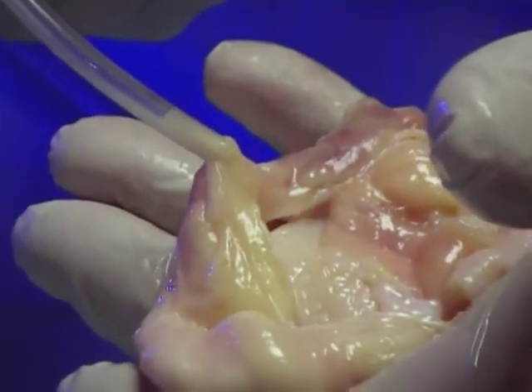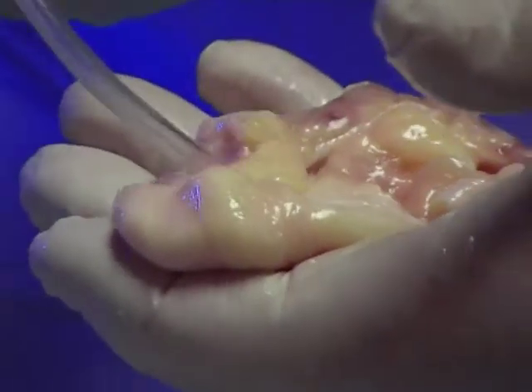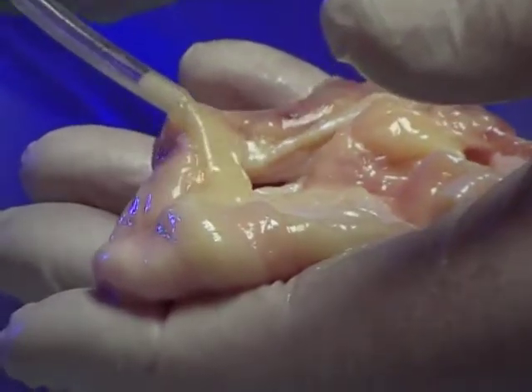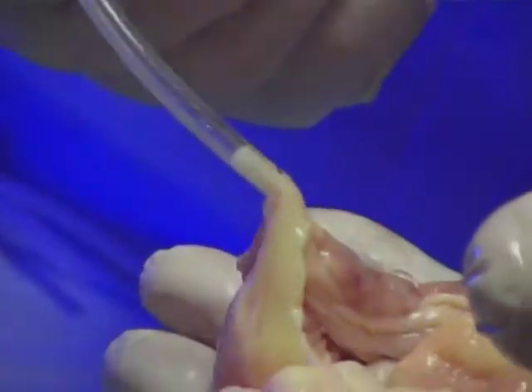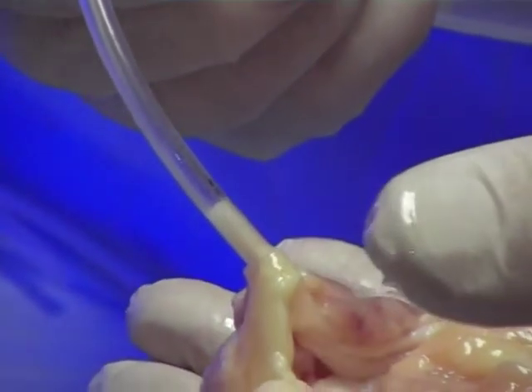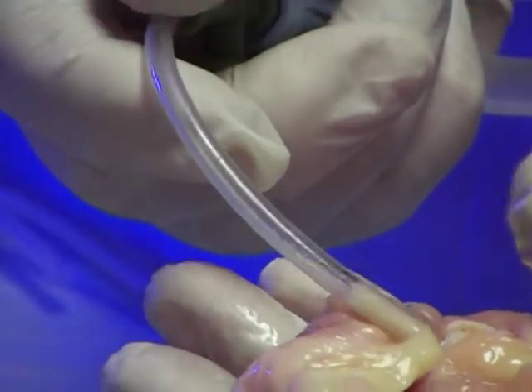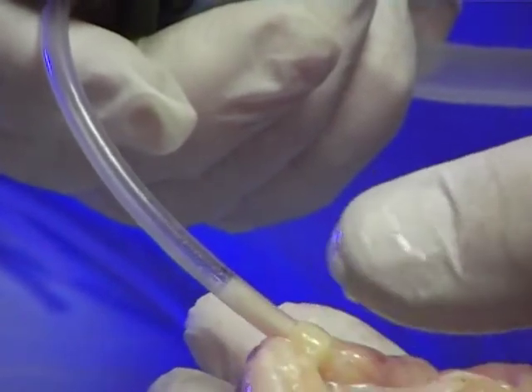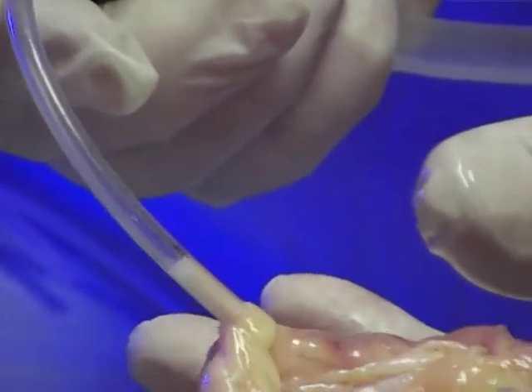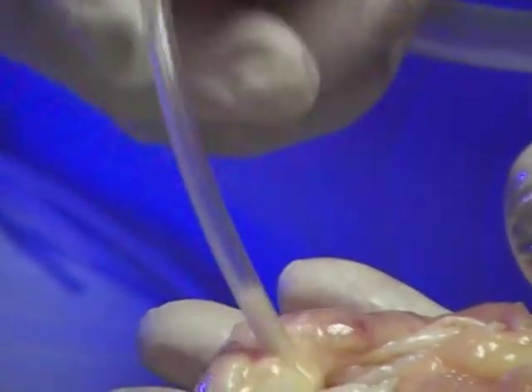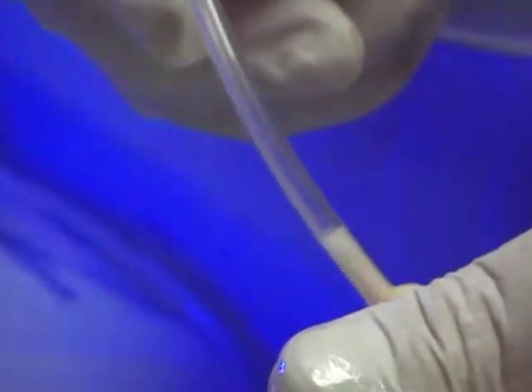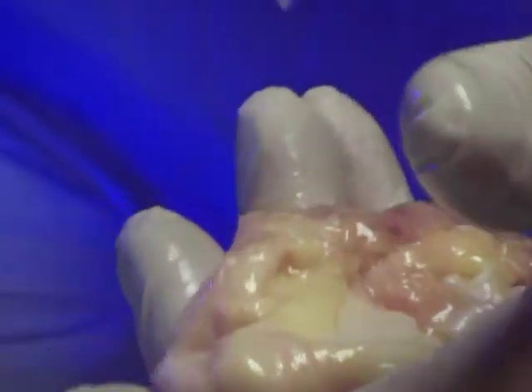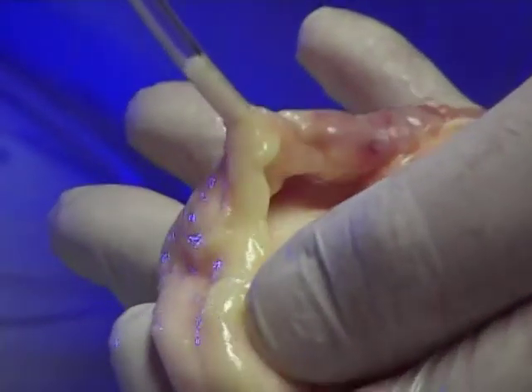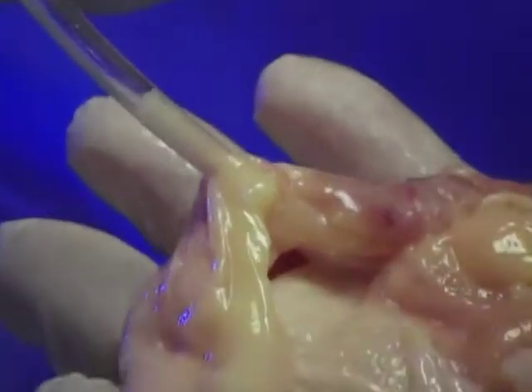It actually grabs more tissue. So in an effort to try and get the mucus out, now what's happened is I can almost lift this up. That's a soft piece of tissue, so you can see how much it's grabbing it. Now what happens is that it gets clogged in there, and then you turn off the suction, but it's now lodged within the cavity and the catheter, and the doctor will then have to come in with forceps and try to eliminate it. You can see this is continuing to move. Now the nurse may think she's in there suctioning, and then when she pulls to disengage, that's where the tears occur. That's when the tissue gets torn. Once again, the skin of chicken is much more dense and much more thick than a neonate's. But there's an example of what can happen when you suction with a device with only one hole.